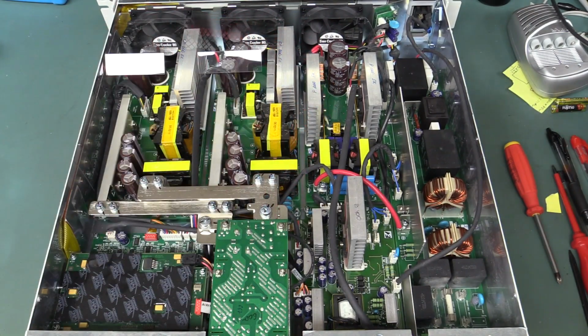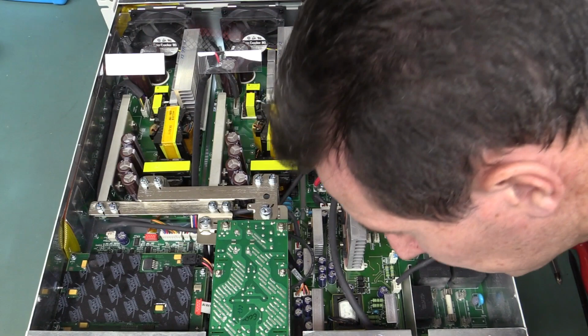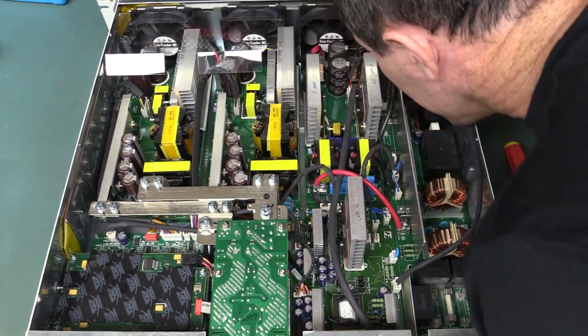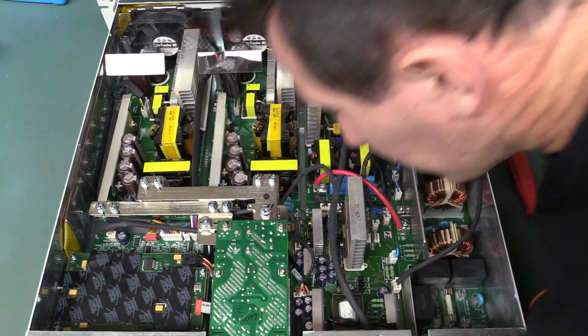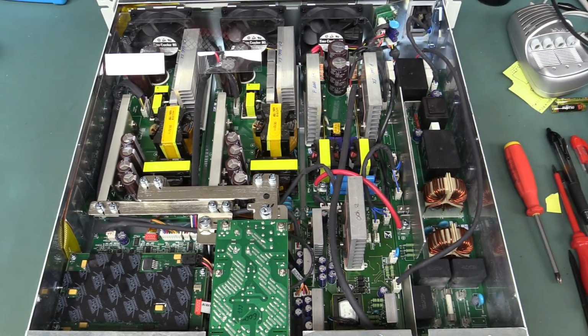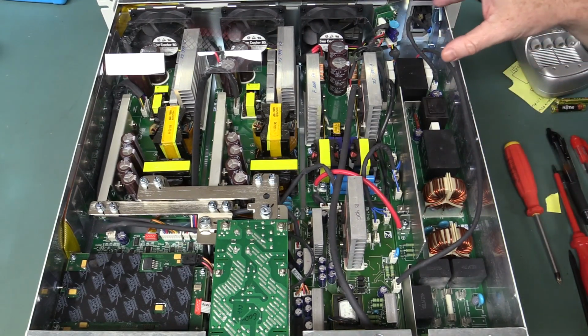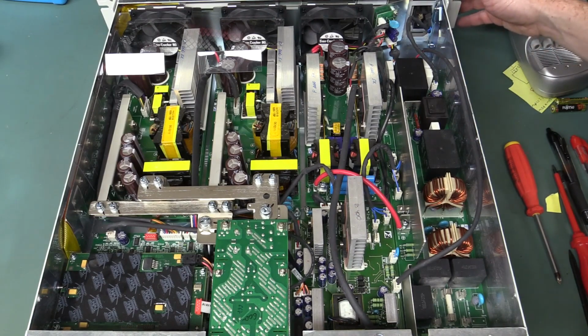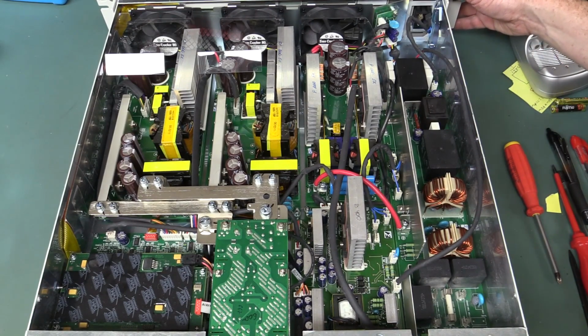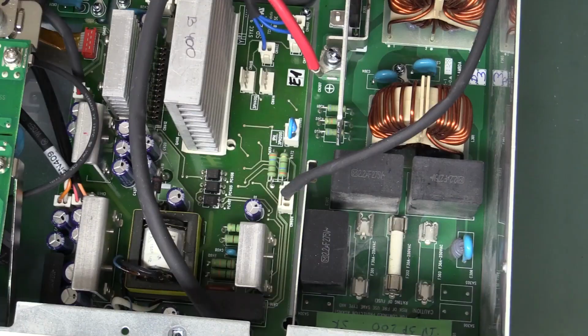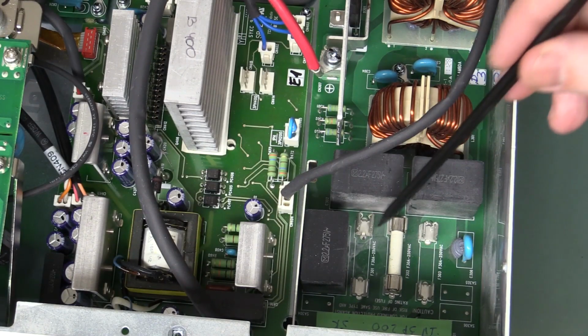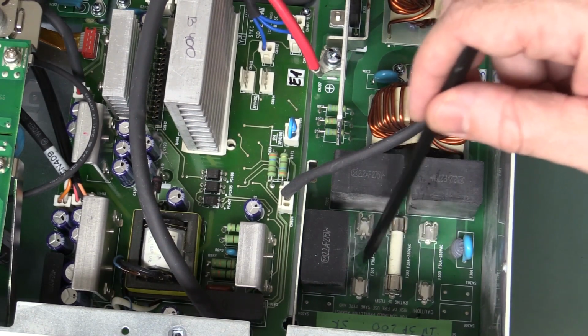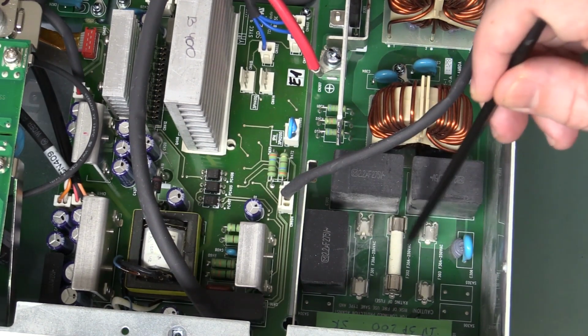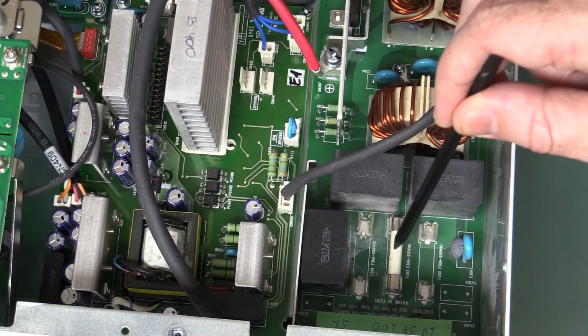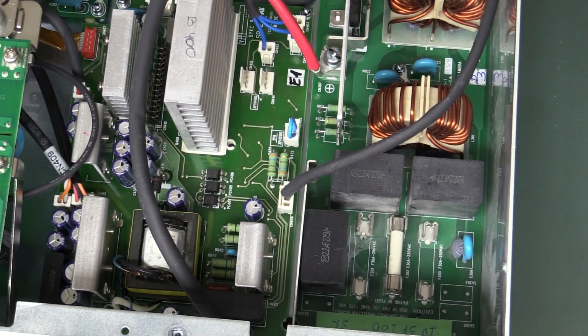Beauty. Now, first thing I'm going to do is give it an old sniff test. No, I can't smell anything really burnt. So, visually, at first glance, I don't see anything wrong with this thing. And, oh, I can see, yep, down here. Well, it's not actually something wrong that's blowing up, but two of the fuses for two of the phases here are missing. These are, look, 30 amp. Whoa, big beast, HRC ones too. 30 amps, 250 volt rated fuse.